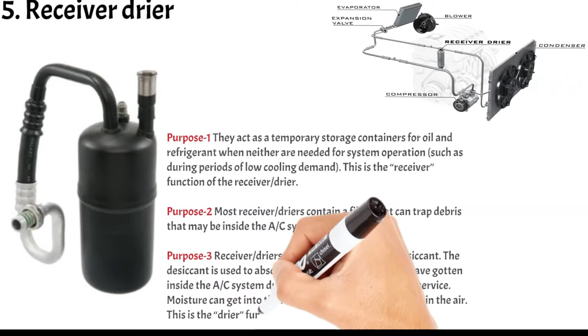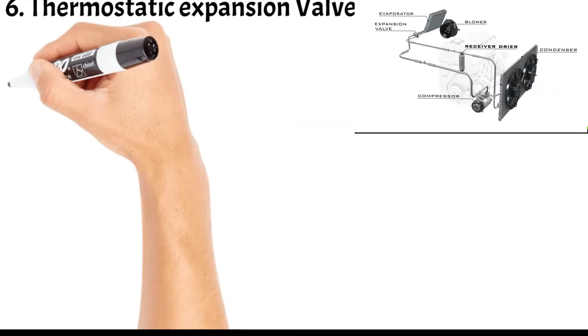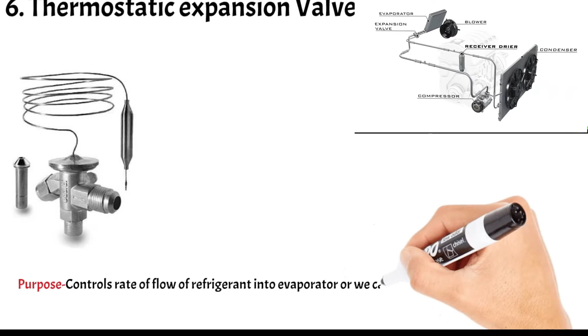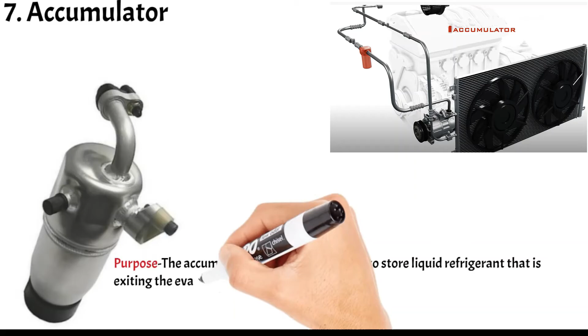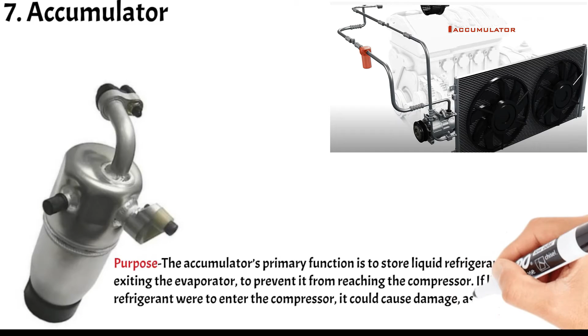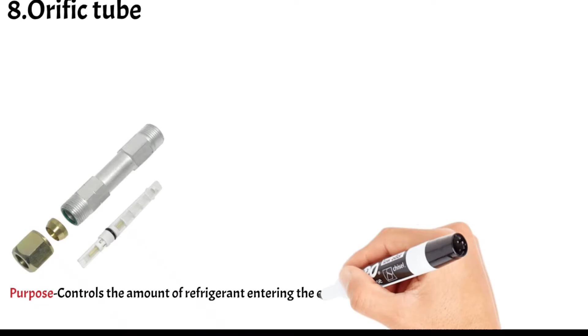Number 6 is thermostatic expansion valve. It controls rate of flow of refrigerant into evaporator, or we can say it controls the pressure of liquid refrigerant flowing inside the evaporator. Number 7 is accumulator. Its primary function is to store liquid refrigerant that is exiting the evaporator to prevent it from reaching the compressor. If liquid refrigerant were to enter the compressor, it could cause damage as the compressor is not designed to pump liquid, only vapor. Number 8 is orifice tube. Orifice tube controls the amount of refrigerant entering the evaporator, or we can say it controls the pressure of liquid refrigerant flowing into the evaporator. It is to be noted that accumulators are only used on systems that contain orifice tubes.